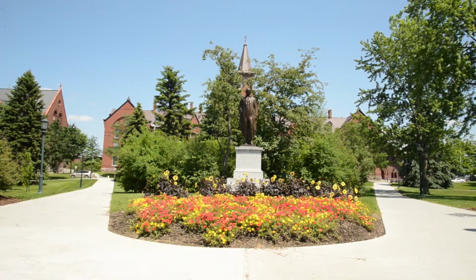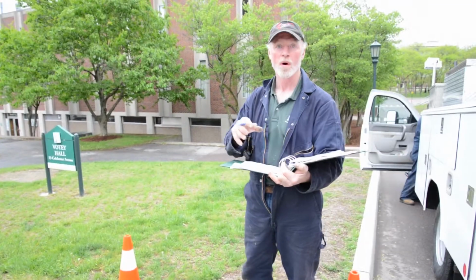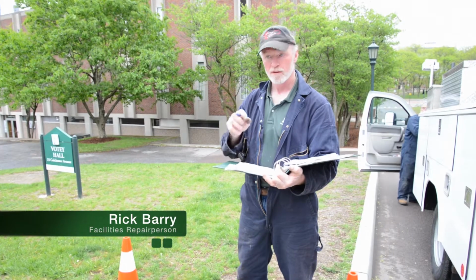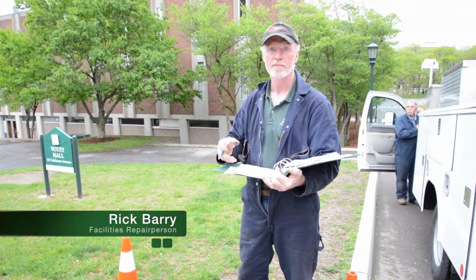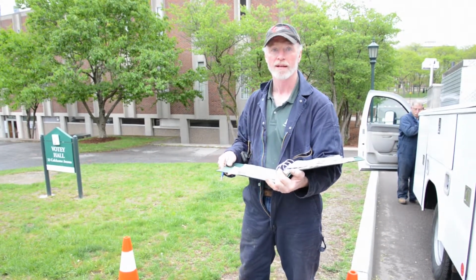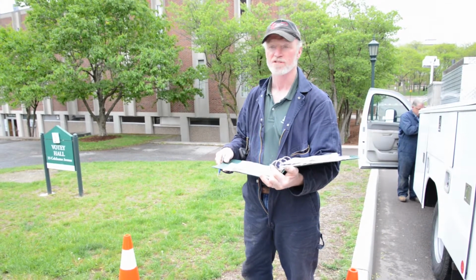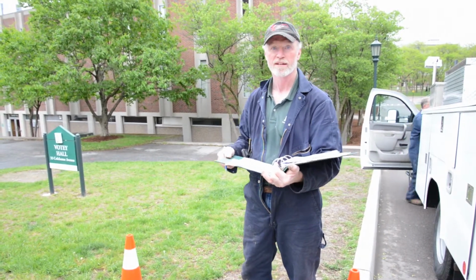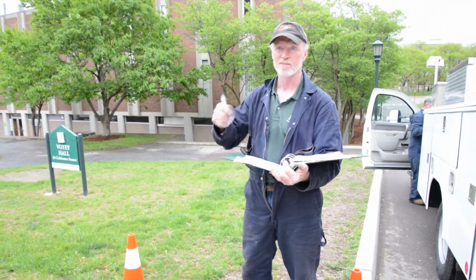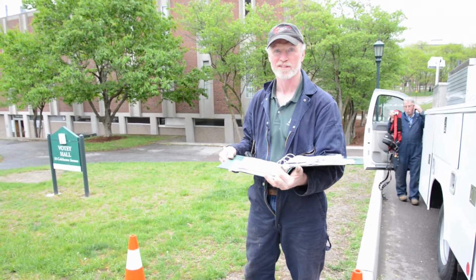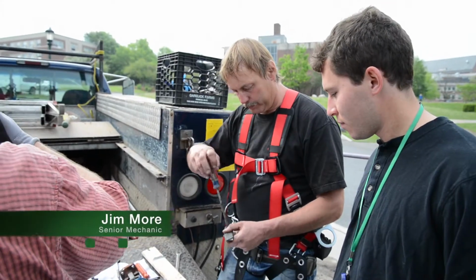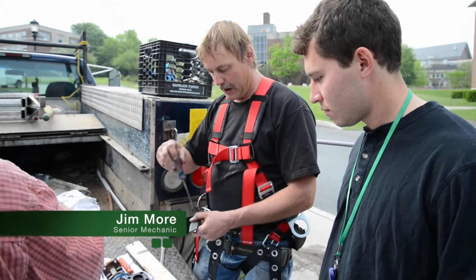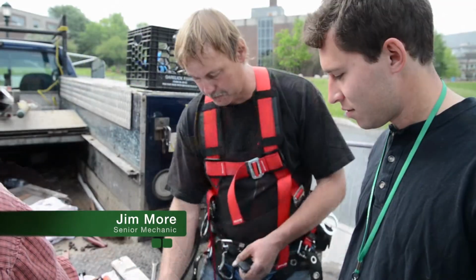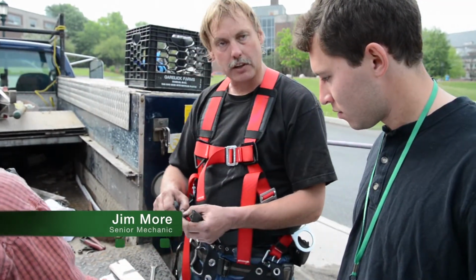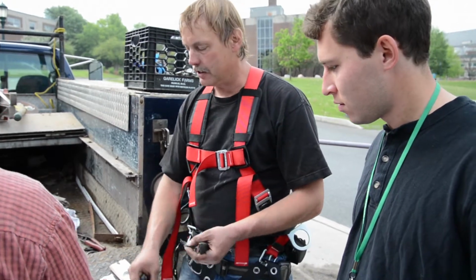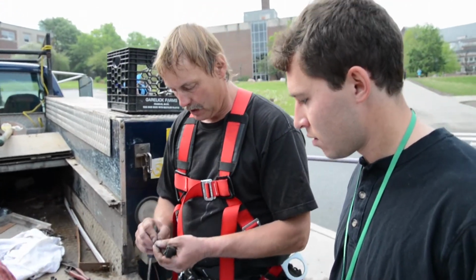We're checking all the valves, steam valves, adding to them if need be, tightening down the ones that don't need more packing in them. It's a process done every year, campus-wide. Underground, above ground, in buildings, wherever there's a steam valve, it gets done. A lot of people that buy these valves don't pack them every year. So the metal mesh type graphite is put in to last longer than the rope type.